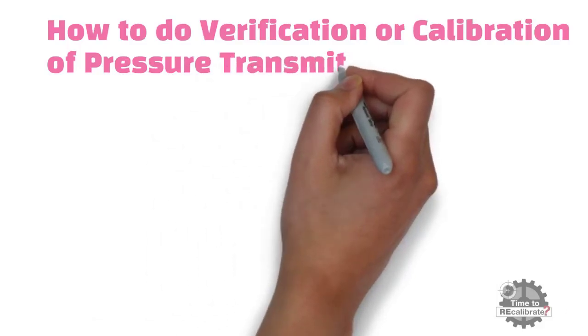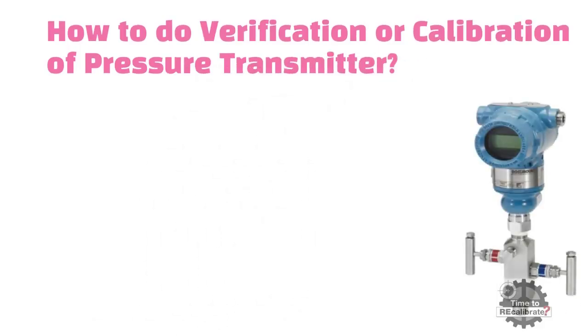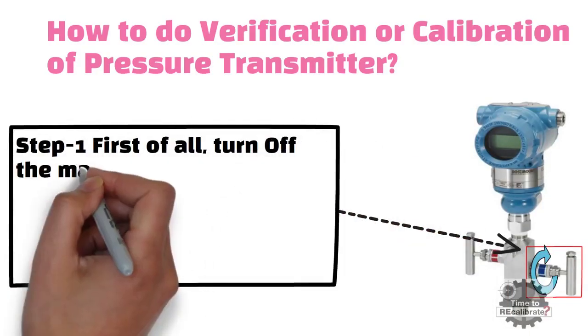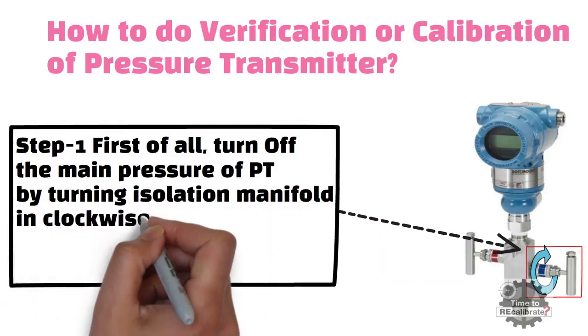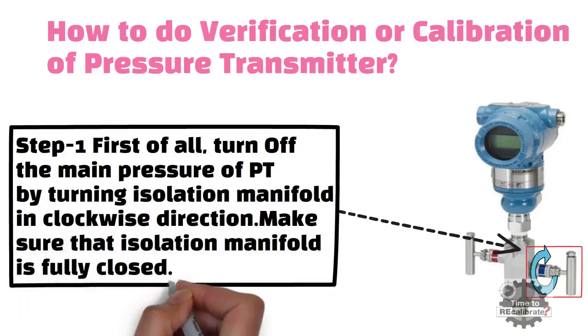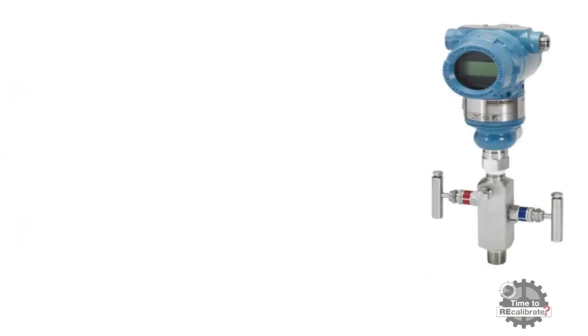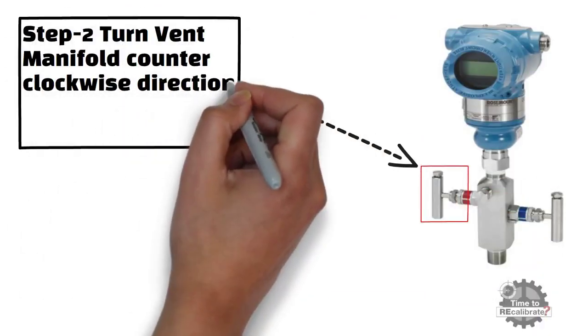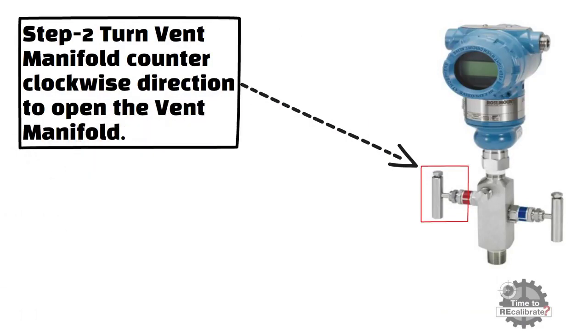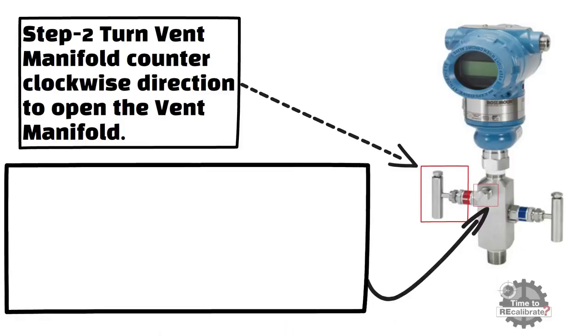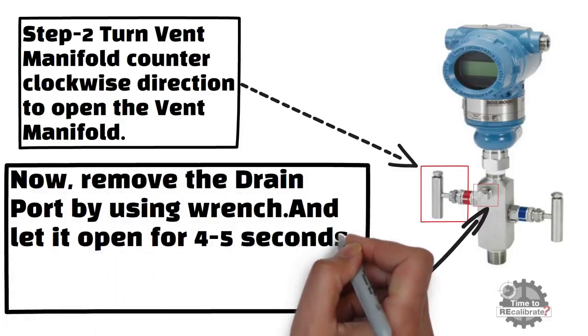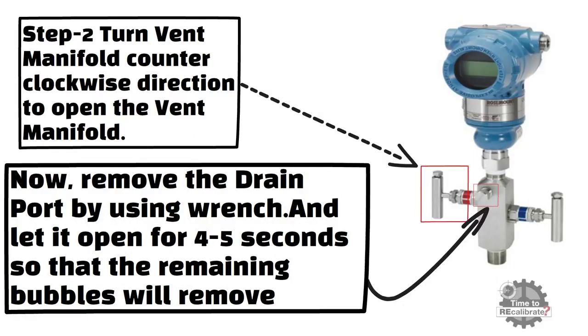How to do verification or calibration of pressure transmitter? Step 1. First of all, turn off the main pressure of pressure transmitter by turning the isolation manifold in clockwise direction. Make sure that the isolation manifold is fully closed. Step 2. Turn the vent manifold in anti-clockwise direction in order to open the vent manifold. Step 3. Now, remove the drain port by using a wrench. And let it open for 4 to 5 seconds so that remaining bubbles will be removed.